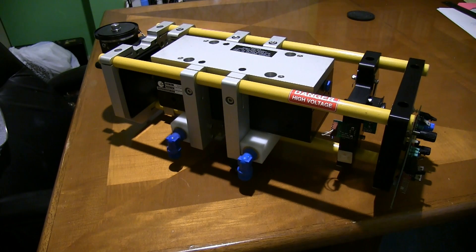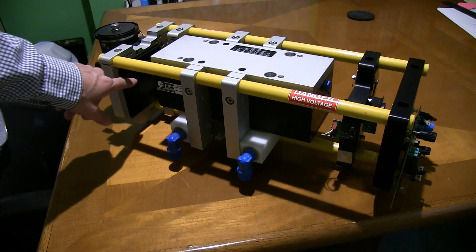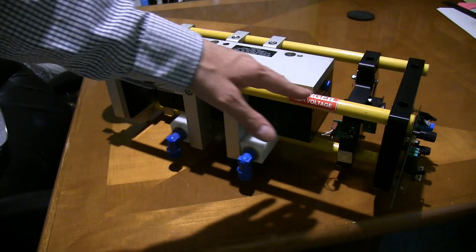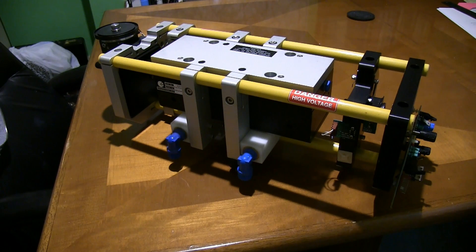On this laser our mirrors are quite some distance away from the actual cavity, so we've got one in this housing and we've got one in this housing. These rails as you can see are designed to keep the mirrors parallel to each other even when we've got expansion and contraction. It will expand and contract still being parallel, which is naturally crucial for the laser to continue operating correctly.